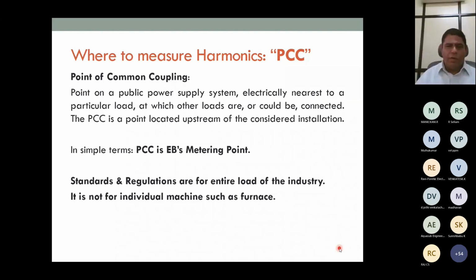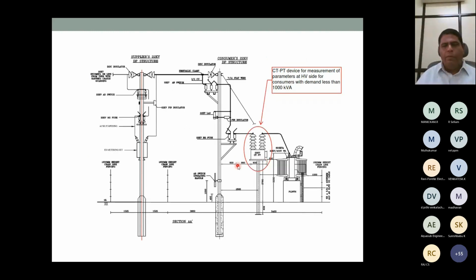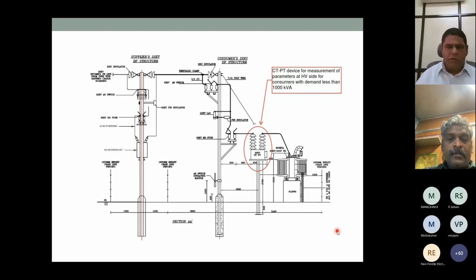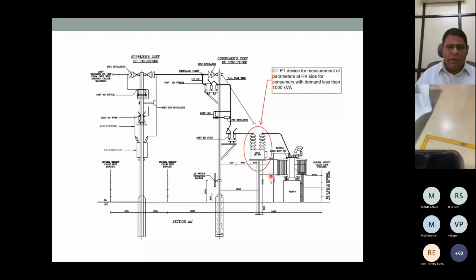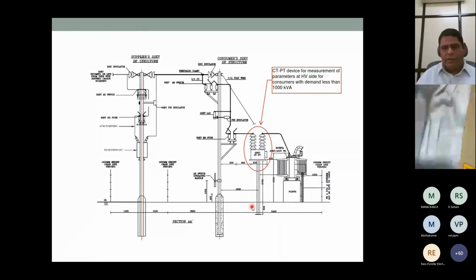We have to measure only on the HT side, that is the high voltage side, before our transformer. Some people will not be able to measure harmonics with their own meters because they may not be using vacuum circuit breakers on their HT side. So for them, they have to use a CTPT, exactly like what the electricity board is using. This CTPT has to be installed, and from this CTPT we can take wires and measure.